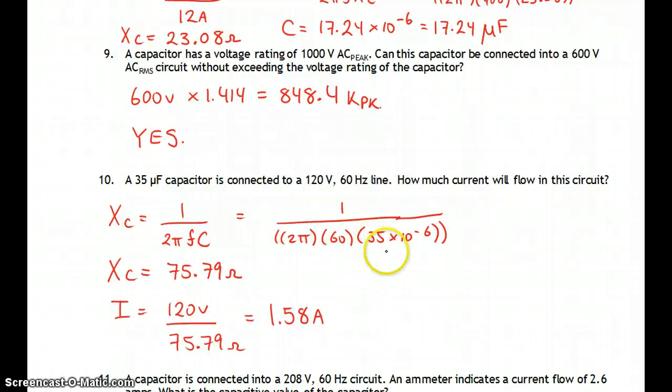We're going to put in 35 microfarads. Remember, the EXP button does the times 10 for you. 35 EXP or EE button to the negative 6 gives you 75.79 ohms. 120 divided by that reactance gives us 1.58 amps.